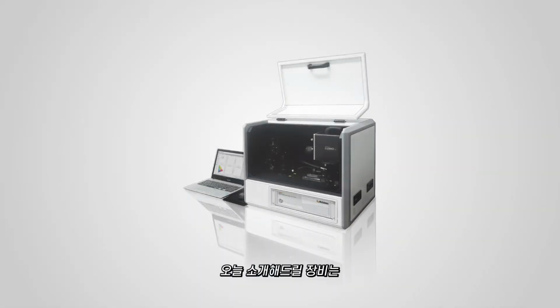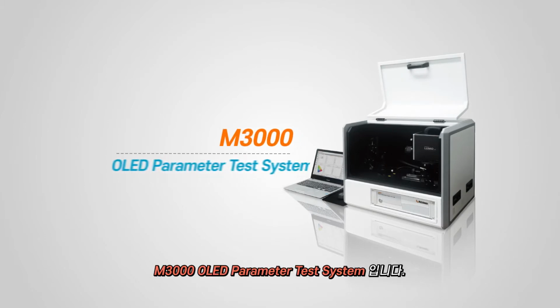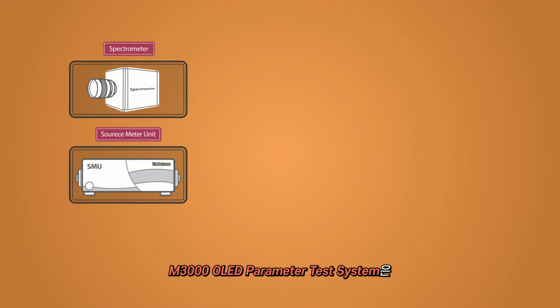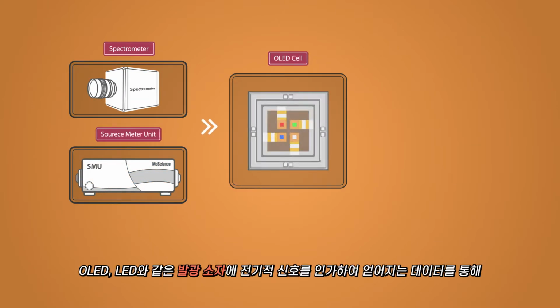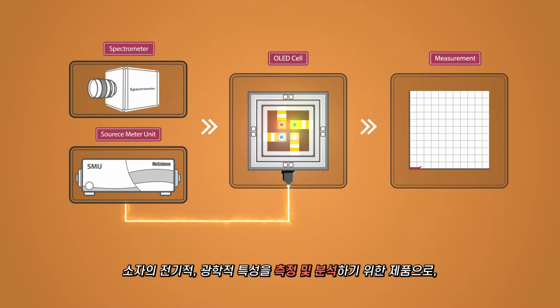Hello, the equipment to be introduced today is the M3000 OLED parameter test system. The M3000 OLED parameter test system is equipment which analyzes light-emitting devices' electrical and optical characteristics by applying electrical source signals to the device and analyzing the resulting output signals.